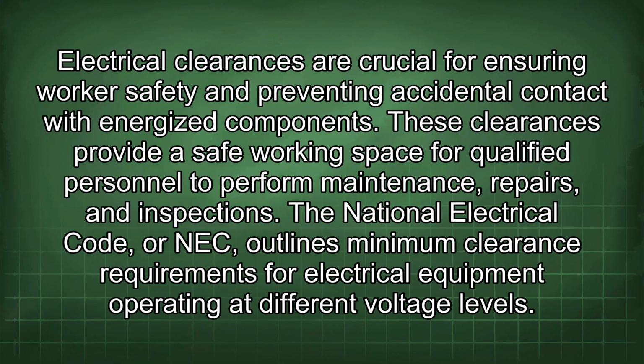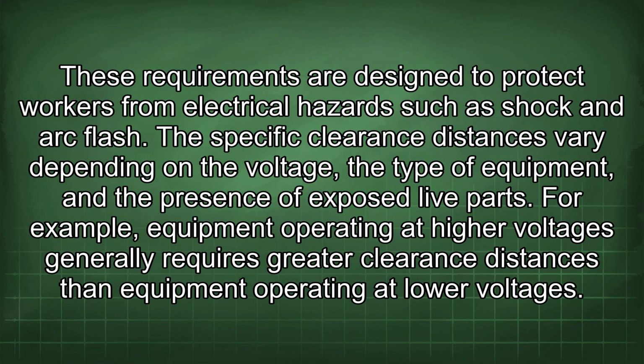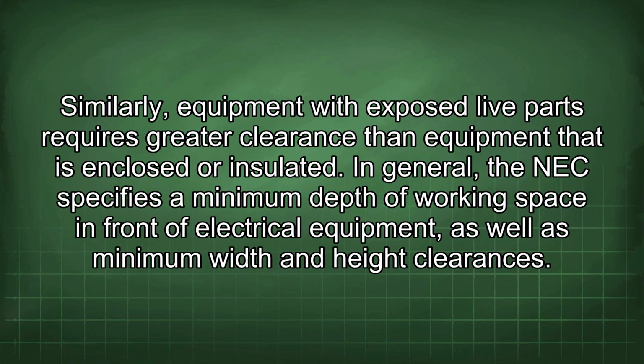These clearances provide a safe working space for qualified personnel to perform maintenance, repairs, and inspections. The National Electrical Code, or NEC, outlines minimum clearance requirements for electrical equipment operating at different voltage levels. These requirements are designed to protect workers from electrical hazards such as shock and arc flash. The specific clearance distances vary depending on the voltage, the type of equipment, and the presence of exposed live parts. For example, equipment operating at higher voltages generally requires greater clearance distances than equipment operating at lower voltages. Similarly, equipment with exposed live parts requires greater clearance than equipment that is enclosed or insulated.